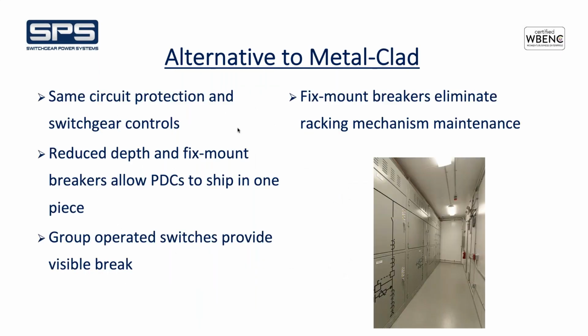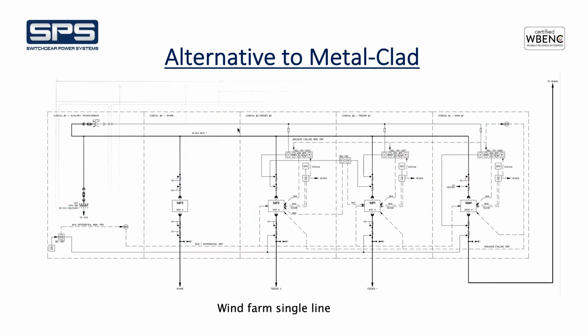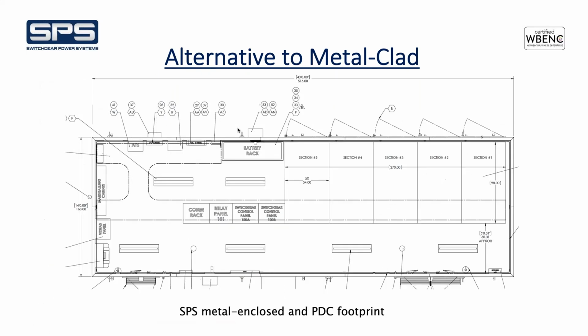The e-house layout was. So you said there's about 12% savings. What is the short circuit rating on those metal enclosed switchgear? Is it 31.5 or 12 or 25 kA? I believe this one was 31.5 kA. Okay. So with the one incoming 3 feeder, okay, yeah, this looks good. Okay.